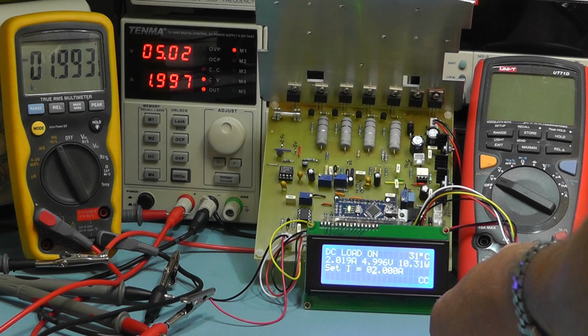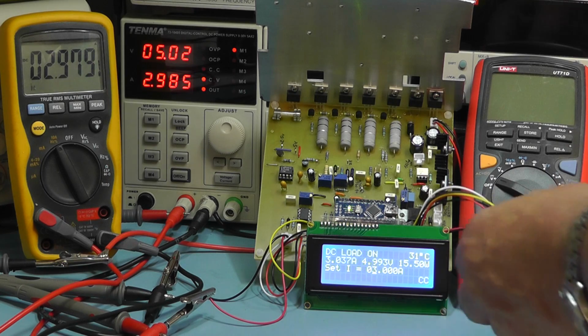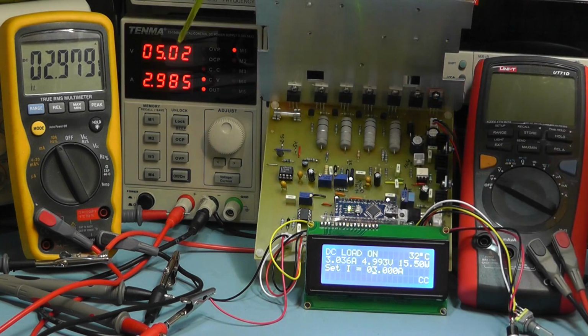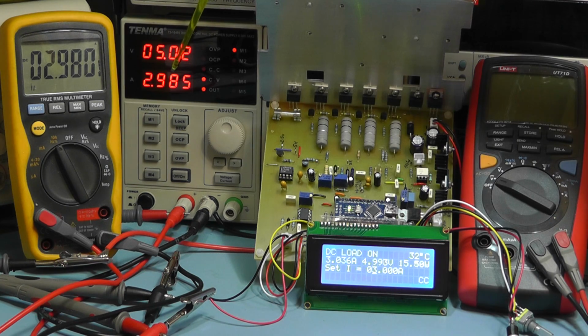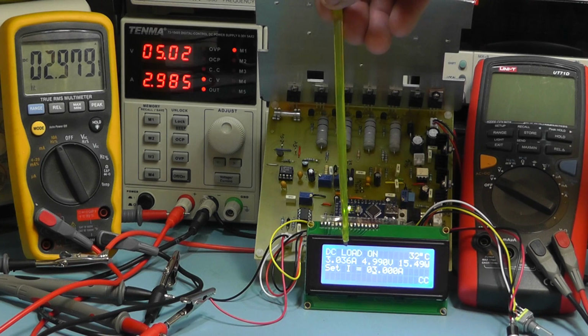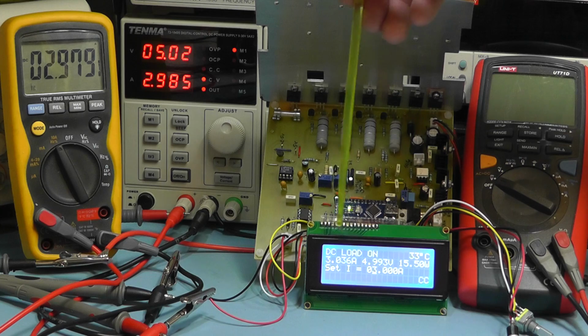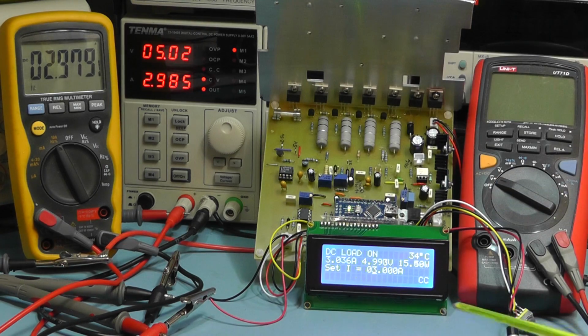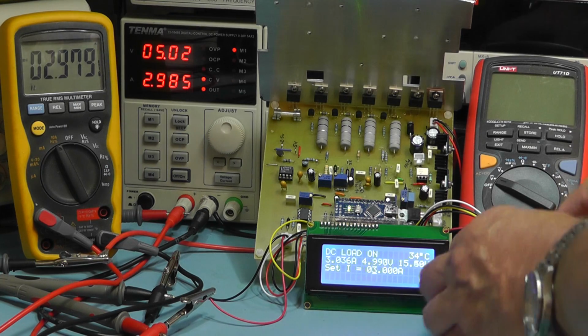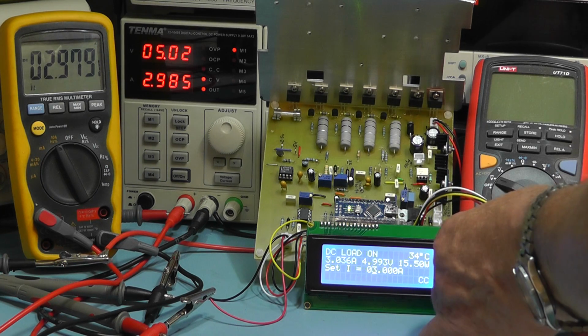Let's take it up to 3 amps. We're slightly down there on the power supply, and slightly up there on the DC load. So there's a slight adjustment error there that we need to address, and we need to have a further look at that on the DC load. But other than that, it does appear to be working.